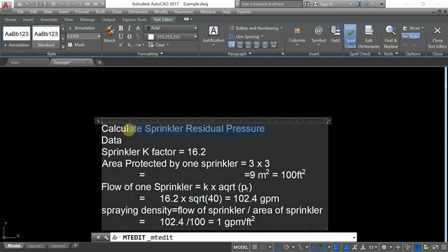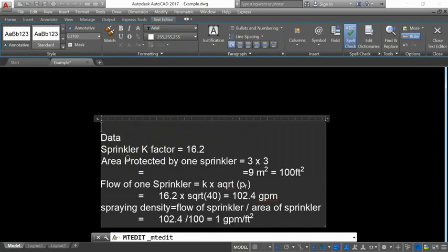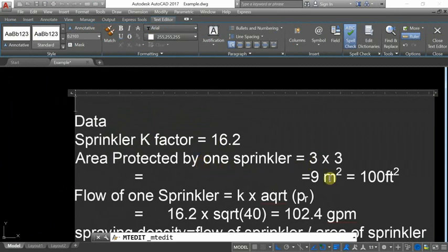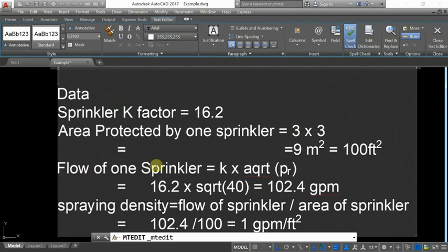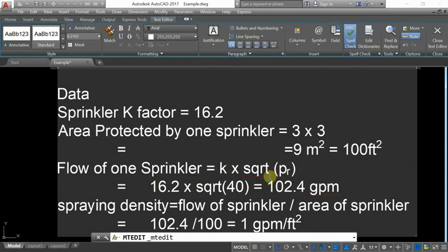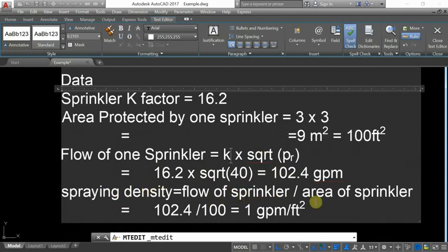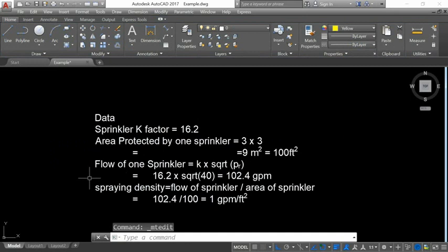We calculate the sprinkler discharge density as follows. The k-factor is 16.2. The area protected by one sprinkler is 3 m × 3 m, which is approximately 100 square feet. The flow of one sprinkler is Q = k × √P = 16.2 × √40 ≈ 102.4 gpm. The sprinkler density is the flow divided by the coverage area: 102.4 gpm ÷ 100 ft² = approximately 1 gpm per square foot. This is how you calculate density when you have the k-factor and the area per sprinkler.